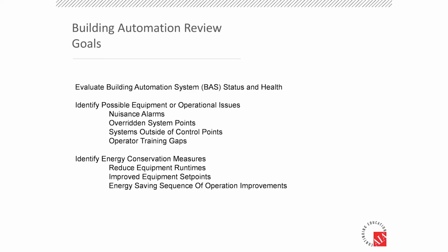Then we look at possible issues, like nuisance alarms. If I sit down at an operator workstation and there are 500 alarms that haven't been answered, that tells me they're not using this workstation and could be missing information. Do we have overridden system points—overriding schedules, set points, or equipment on and off? This tells me they may be trying to compensate for some issue by overriding that information, and the system isn't operating in full automatic, so it's not giving them the most value.